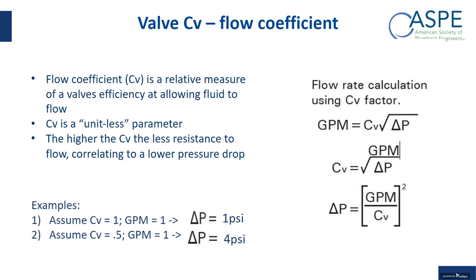So one of the things that seems to be coming up more and more with thermostatic balancing valves and with manual balancing valves is the CV of a valve. I was surprised, but there are a number of engineers and designers out there that don't really know what CV is. CV stands for flow coefficient. It's a unitless parameter. There's nothing attached to it like inches or gallons per minute or degrees Fahrenheit. It's just basically a number. The higher the number, the less resistance to flow. The lower the number, the more resistance to flow. So the lower the CV for a given flow rate, you're going to have a higher pressure drop.